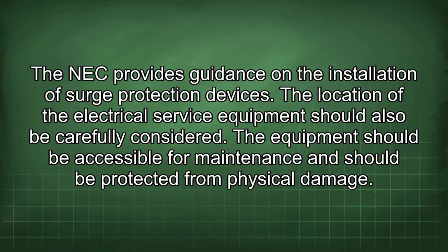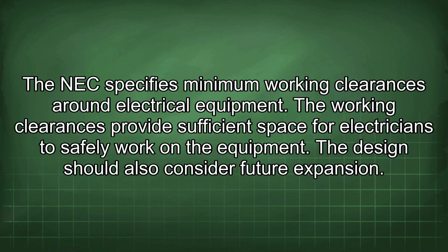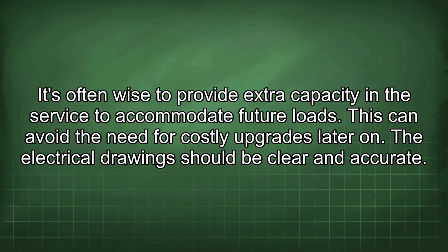The location of the electrical service equipment should also be carefully considered. The equipment should be accessible for maintenance and should be protected from physical damage. The NEC specifies minimum working clearances around electrical equipment. The working clearances provide sufficient space for electricians to safely work on the equipment. The design should also consider future expansion. It's often wise to provide extra capacity in the service to accommodate future loads. This can avoid the need for costly upgrades later on.